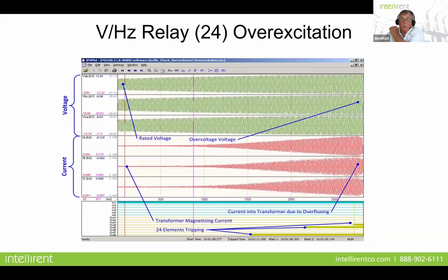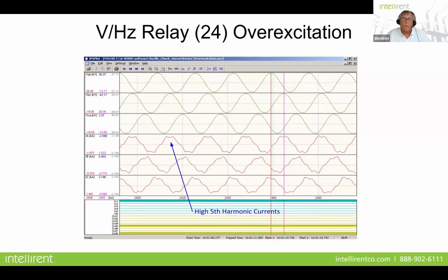And this is what an oscillography would look like in volts per hertz. You'll see the voltage starting to increase, the frequency starting to come down, and this is right when you see the transformer magnetizing current. The one thing that I want to point out here is that a volts per hertz condition can cause the differential element to trip. The problem is the volts per hertz condition may not be high enough to actually trip on overexcitation on that element, but it may be enough to trip the 87 element.